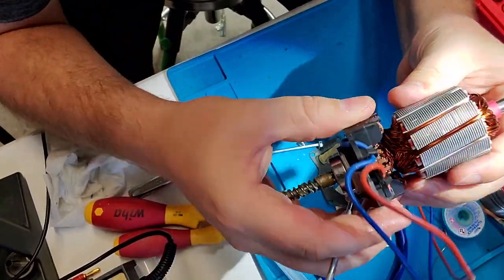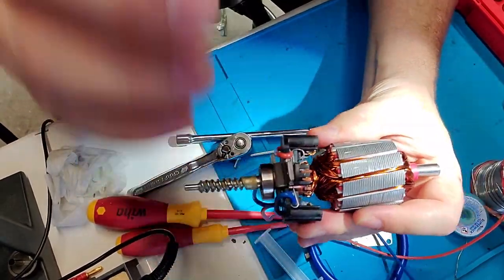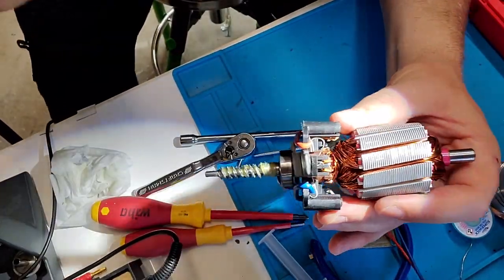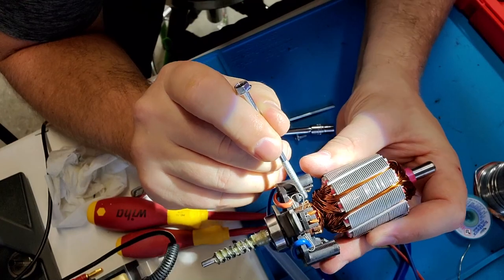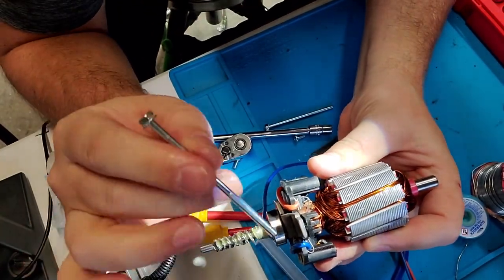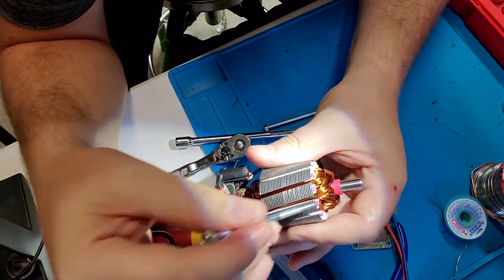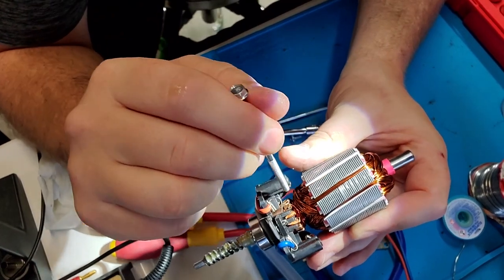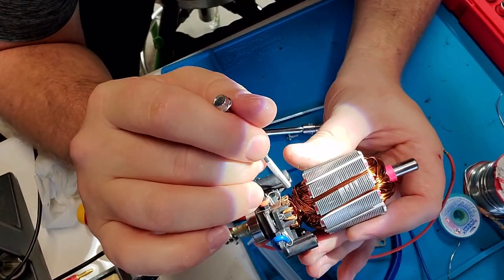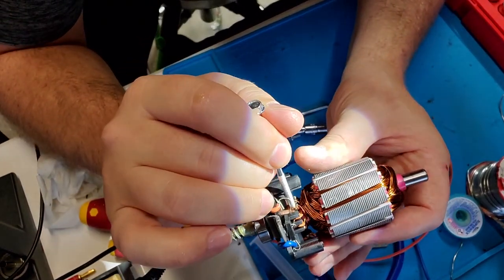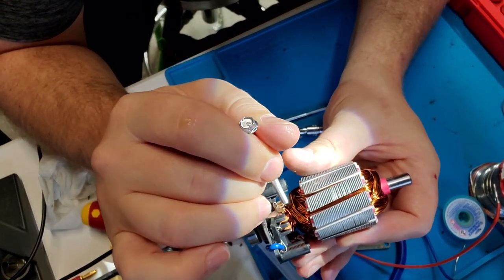You can see that there are grinding marks in the motor right here. So those are balance marks. And what they do is they spin this guy up. They've got it on a chuck and it tells them where to place grinding marks and how deep, how much material to remove. And they do that to balance it up because all things that rotate have harmonics. I've said that before. And the way that you get rid of harmonics or minimize them is you are going to make it as balanced as possible. So even though there's just tiny little scratches like right here in the surface, that still removes enough material that it balances out the rotor.